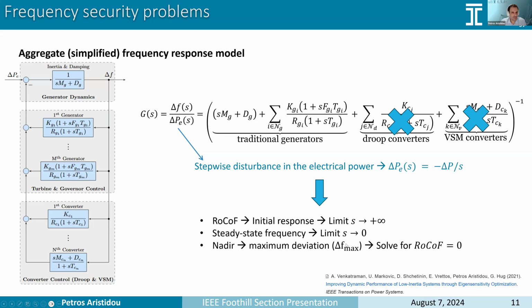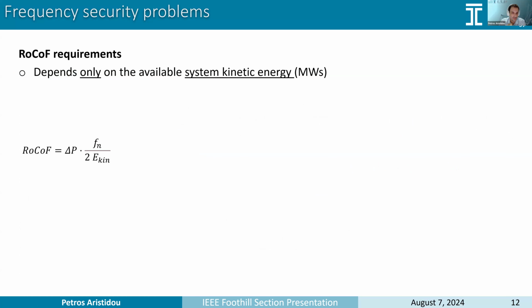Now, using this, we can compare the required reserves that we need with the limits that we have on the different frequency characteristics. For example, if we check the RoCoF requirements, we need to limit the rate of change of frequency within some limits. In the Cyprus system, that is 1.5 hertz per second. So using the equation that we found, we see that the rate of change of frequency only depends on the system kinetic energy. Of course, that's very well known. It comes from the swing equation.